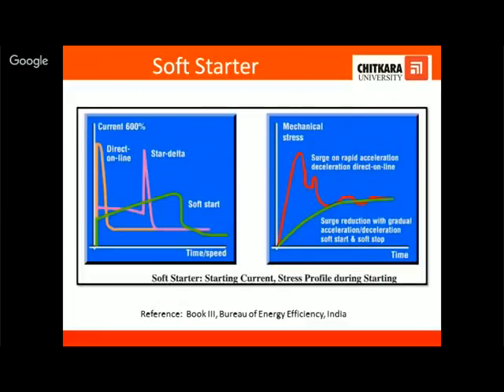Now I have just taken the 2 examples of a soft starter. There are 2 curves, current versus time, and mechanical stress versus time. If we use a direct online starter or a star delta starter, in both cases we get current surges. But if we are using the soft start, there is a smooth start. The ramp is very smooth, so there is no power surge. And if we talk about mechanical stresses, with direct online starters there are mechanical surges, but with the soft starter the surge is not there and there is a smooth start.